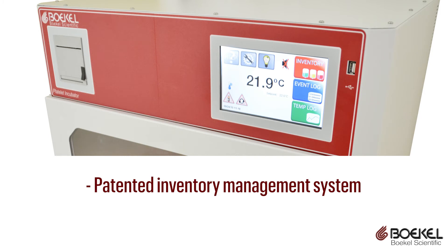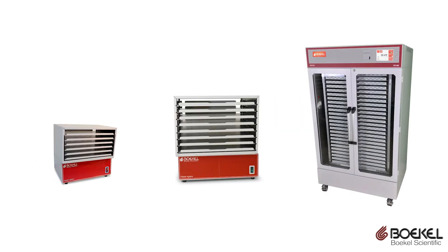The unit also has a large color touchscreen with a patented inventory management system, an easy-to-use calibration process, and an automated high-low temperature alarm testing procedure. Boekel Scientific offers three sizes of platelet storage systems.